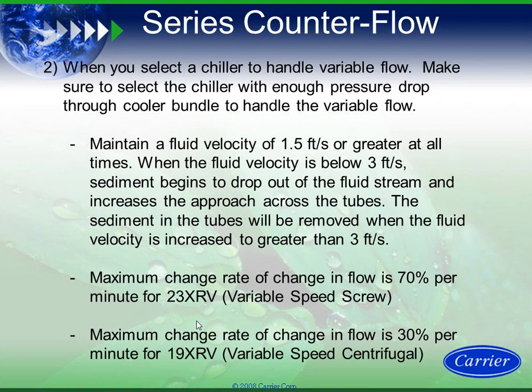On the 23XRV, I have a 70% maximum rate of change. I told you 80 before. That is correct. This is an older slide. They've updated to 80% rate of change of flow on the 23XRV. Maximum rate of change of flow on a centrifugal. Majority of centrifugals without EXVs is 30% rate of change of flow.